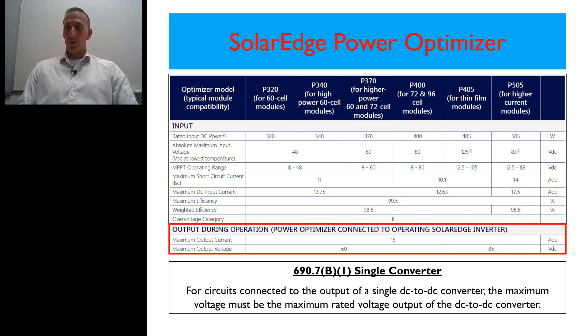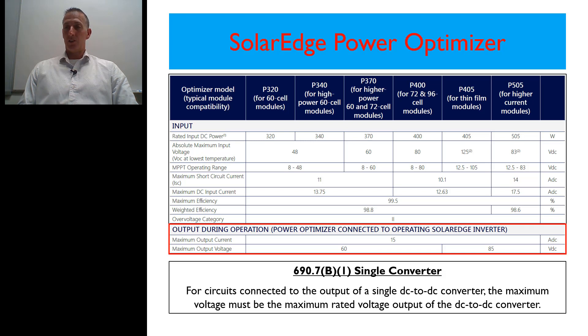If you go up to the next ones — the P405 or the P505 — those jump up even higher to 85 volts DC. So if you have that one single optimizer or converter, if you had just one of those in that circuit, the maximum rated voltage would be the output — either 60 or 85 volts depending on what you're using. That's how you determine the maximum rated voltage for that circuit in relation to the requirements of the 2017 National Electrical Code.